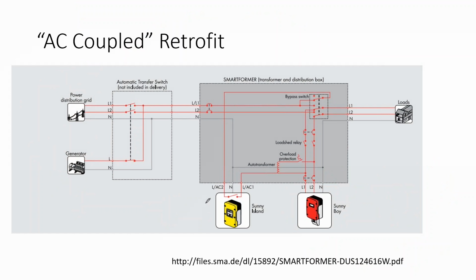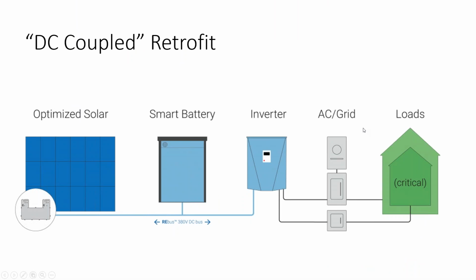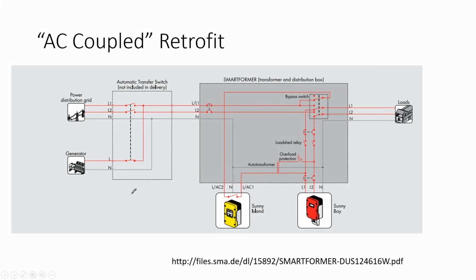You could actually land an off-grid battery inverter onto a generator panel, where here's your main panel and your main that the grid lands onto. A generator panel has a little breaker with a plate on a switch that says either the generator or the grid is going to be on. You could get a cheap battery inverter and put it on that interlock panel, and during a blackout, flick your main off and turn your battery inverter and solar array on. There are cheap ways to jury rig your off-grid or battery retrofit.